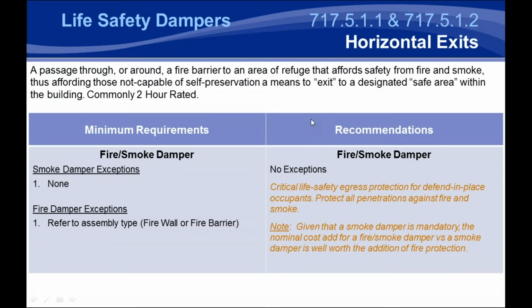Moving on to horizontal exits, I talked a little bit about basically shelter in place, or a means of being able to stay sheltered in a protected area because you can't exit the building for whatever reason. And basically, a horizontal exit is not an exit out of the building, but a passage through or around a fire barrier, whether it's a firewall or a fire barrier, that allows someone to get to an area of refuge because they can't exit a building.